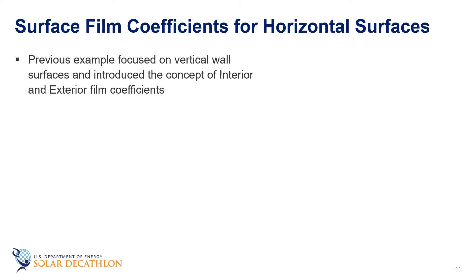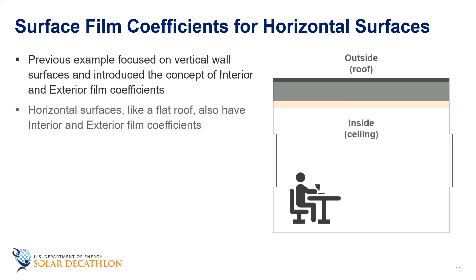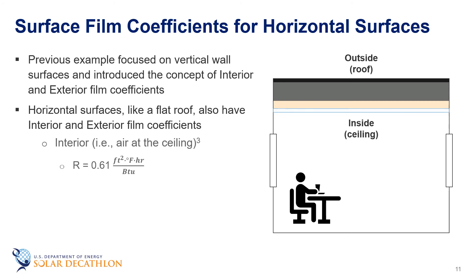So in this episode, we introduced the concept of effective thermal resistance of the air surface on the edge of the wall, called a film coefficient. We gave values for the interior air film coefficient and the exterior air film coefficient based on a vertical wall. Another application of this concept is with horizontal surfaces, such as a flat roof. The interior air film coefficient is actually a little bit less — it is 0.61 for a horizontal surface such as the ceiling — and for the exterior, it's 0.17.